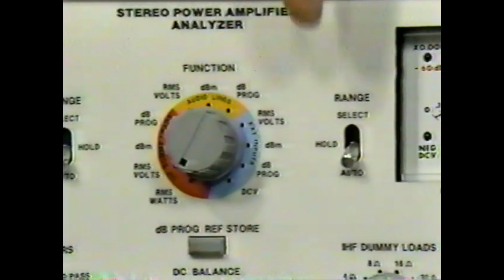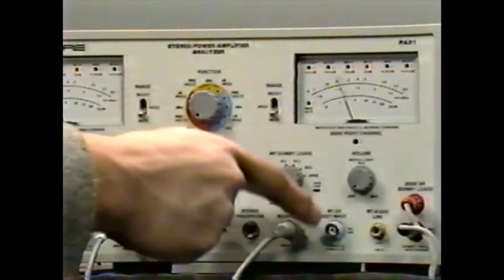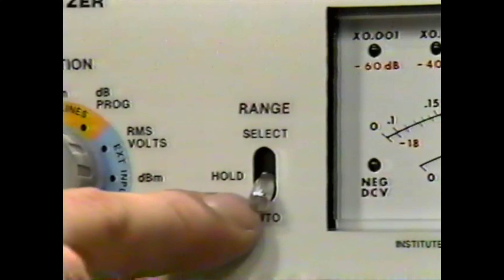First, I must point out that the dummy loads maintain a constant load at the output while you move back through the circuits. When you switch the function switch to any of the positions marked in blue, the meters receive their inputs through the two external input jacks, also marked in blue. These inputs are also auto-ranged with manual override if you want.